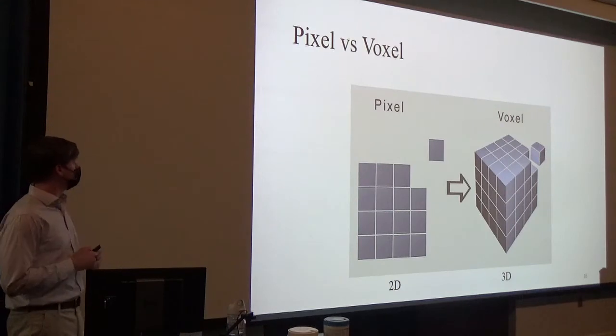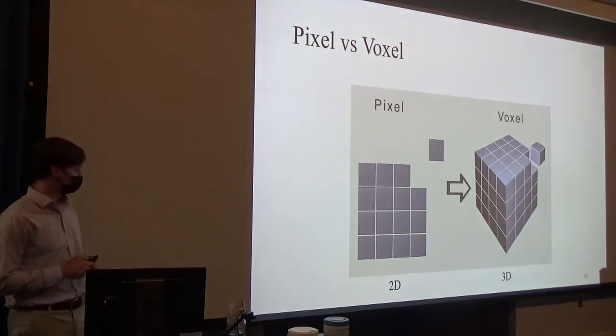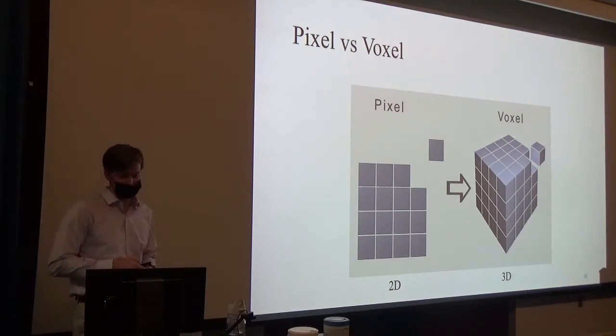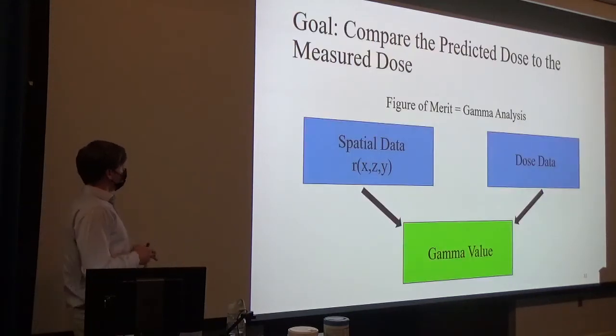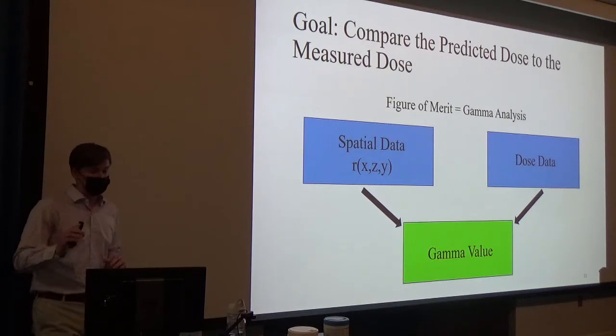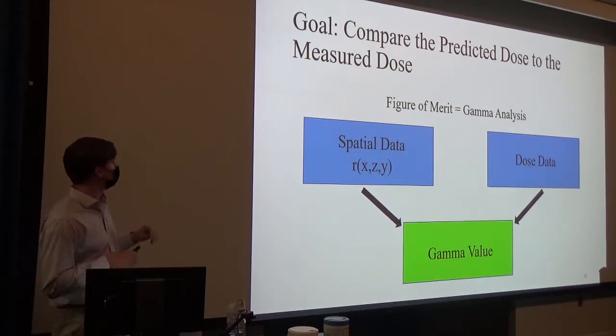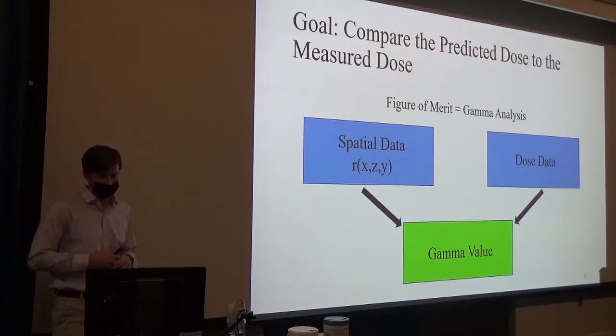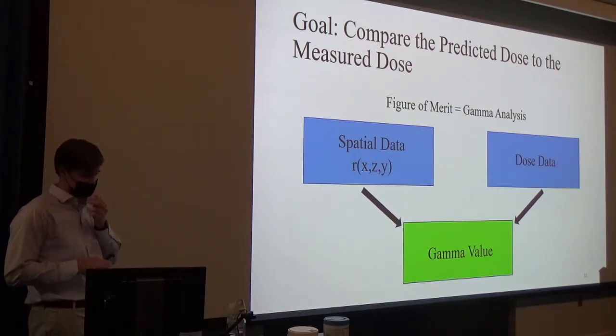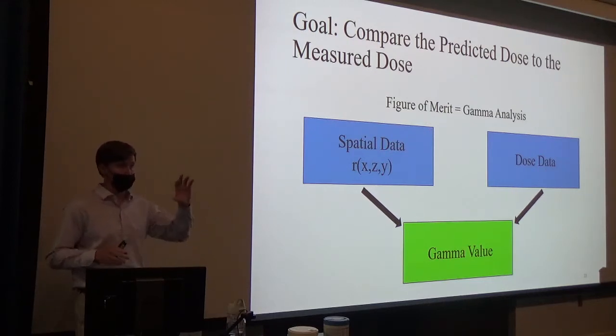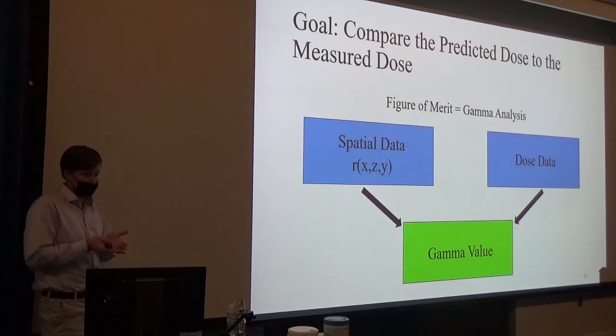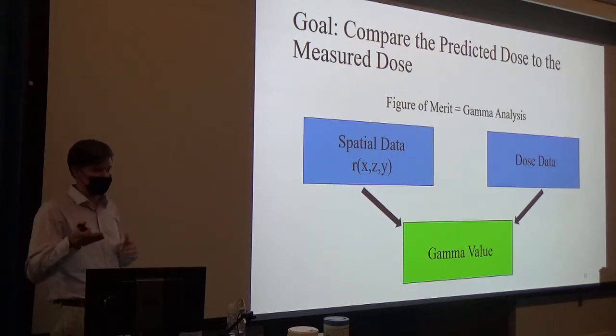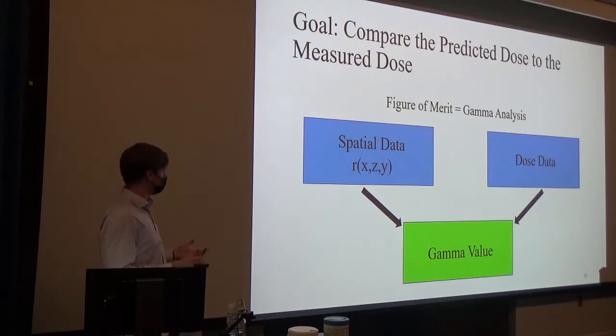Before we go on, it's important to make the distinction between a pixel and a voxel. A pixel is what you see on your television screen — it's two-dimensional. A voxel is the same concept but forms a volume in three dimensions. Our goal is to compare the predicted dose from the treatment planning system to the measured dose scanned in the dosimeter. Both of these datasets have two types of data: spatial data — where you are within the dosimeter — and a dose value associated at that specific voxel. We have two different sets of data and need to combine them into one value for comparison. We do that using the gamma analysis figure of merit.